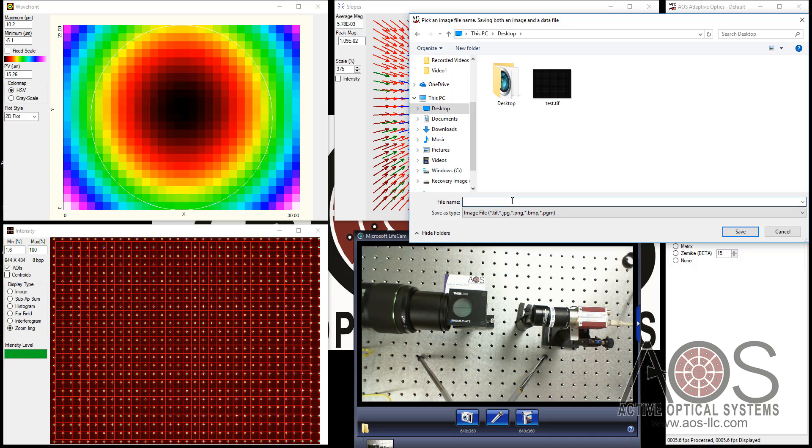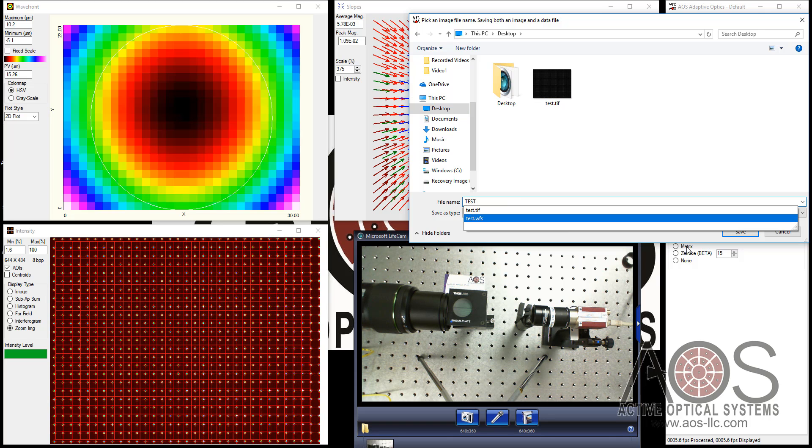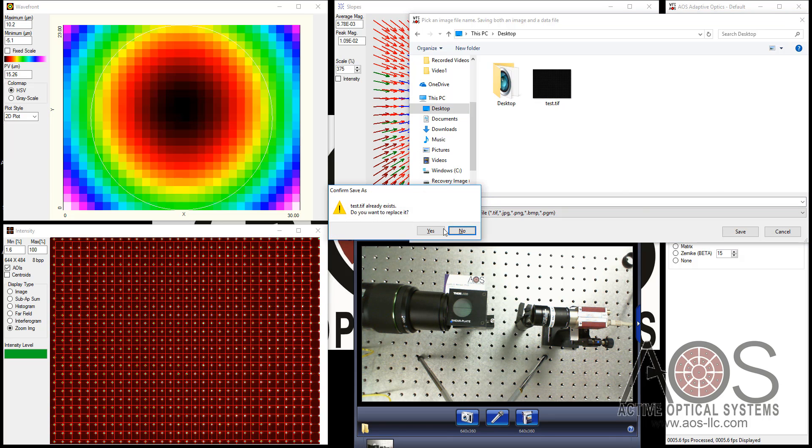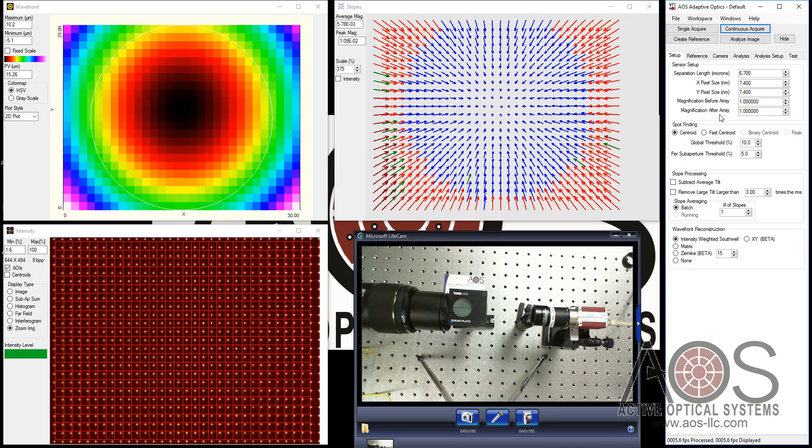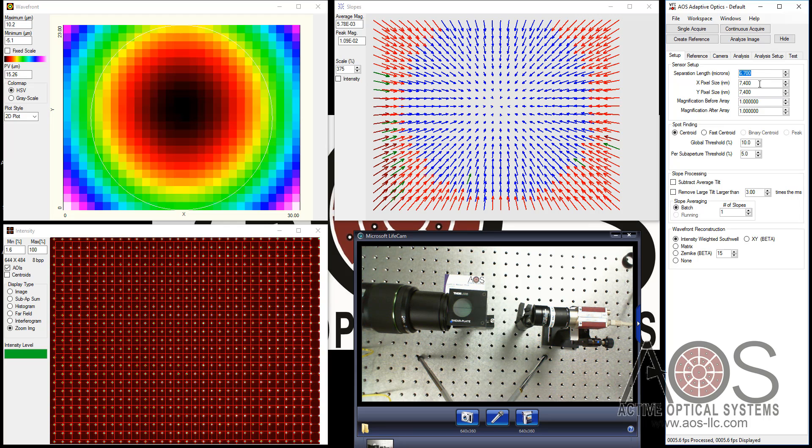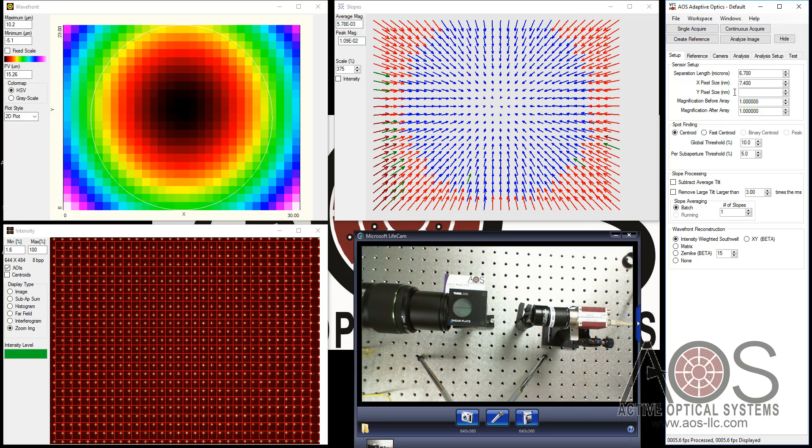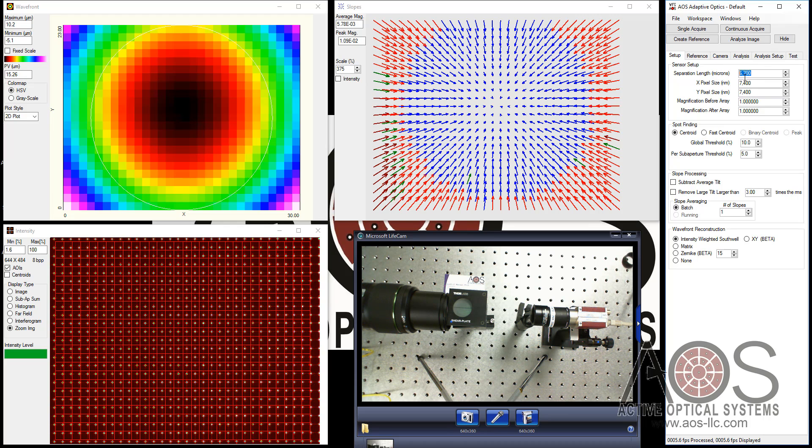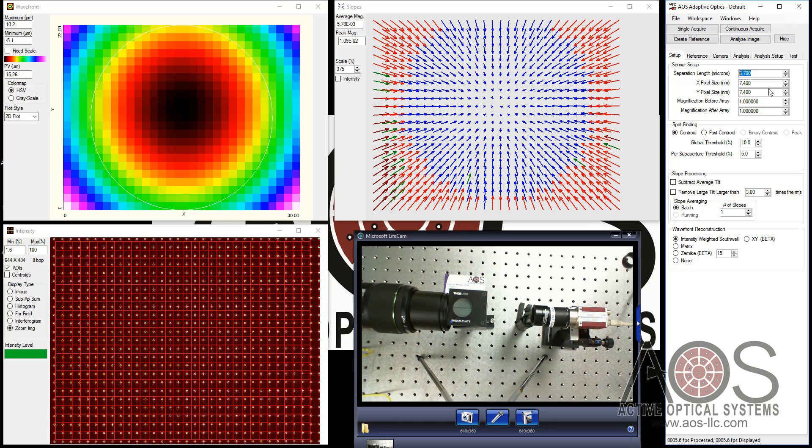So the first thing I'm going to do is save all the data to my desktop here. Desktop. Just say test. Yes, we want to overwrite the old test. By the way, I forgot to mention this. Now that we're starting to make measurements, it's starting to be important. The wavefront sensor software automatically loads the correct pixel sizes. And whatever you've set for the last separation length. In this case, we have a nice wavefront sensor that has about a 6.7 millimeter effective focal length on the lens array. So these are all set properly for us. I forgot to mention that you need to check that.